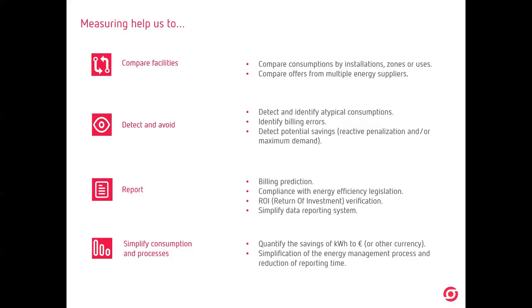By measuring, we will know where we have the maximum consumption and in which use or in which zones, okay? And if we have different installations, the same. We will see which installation is more efficient, which is less, because we will have the total consumption. And we can adopt the good practices of the best efficiency in the rest of the installations that we have. Measuring is also helping us to compare offers from multiple energy suppliers. So if in our country we have more than one utility, and we know how we are consuming, in which period of time, how much energy, etc., we will be able to negotiate with different utilities or the distribution companies, okay, in order to get the better agreement, the better contract, okay?